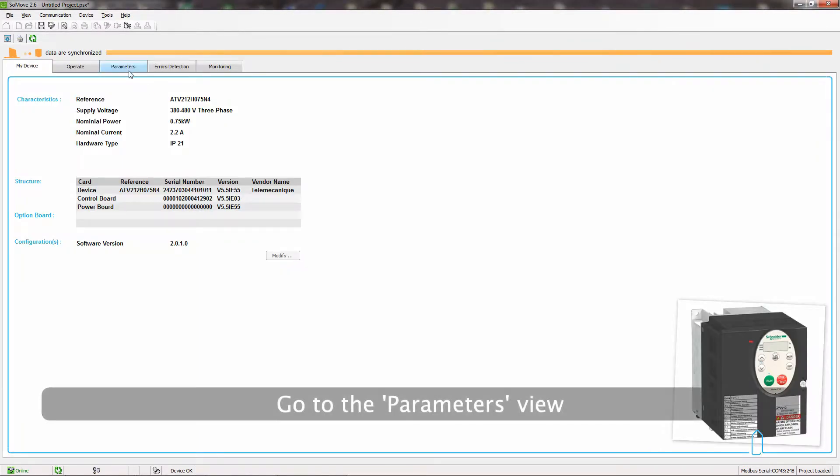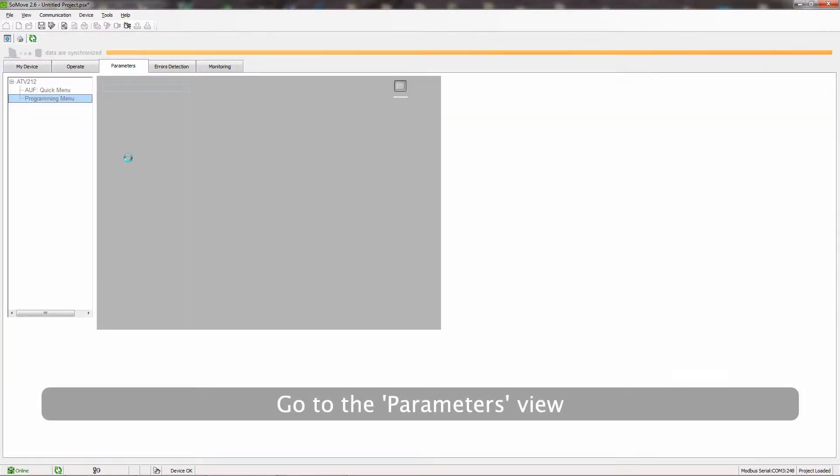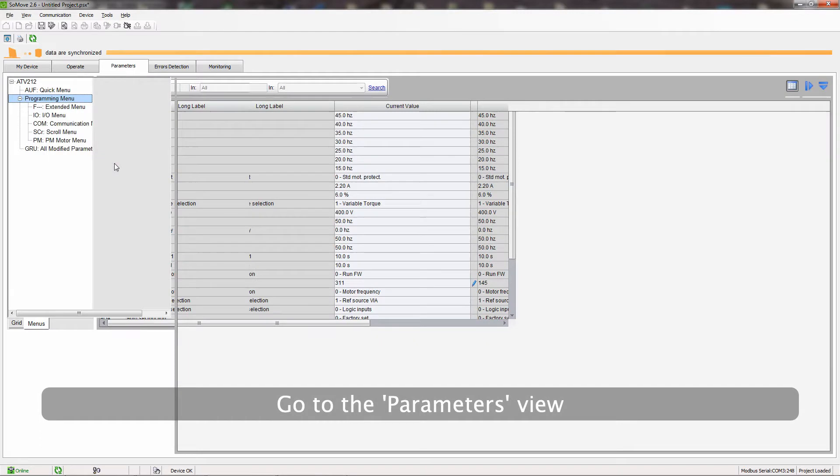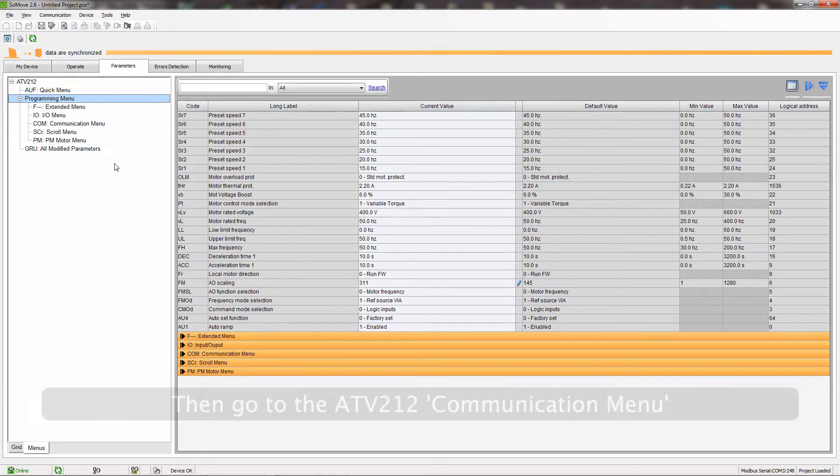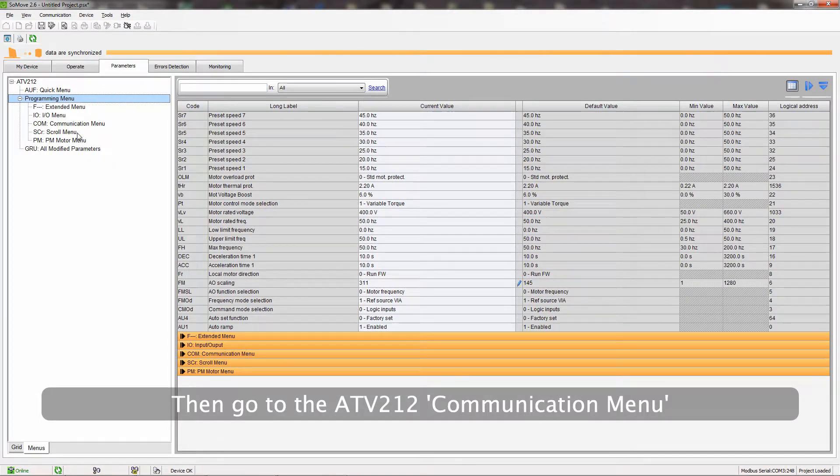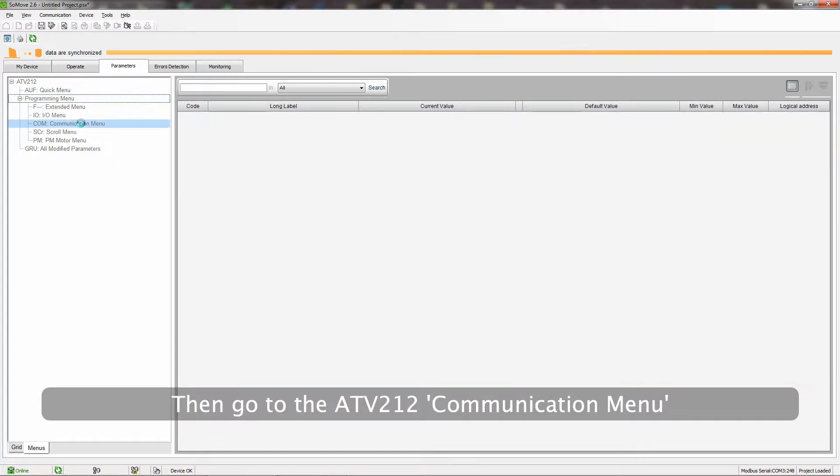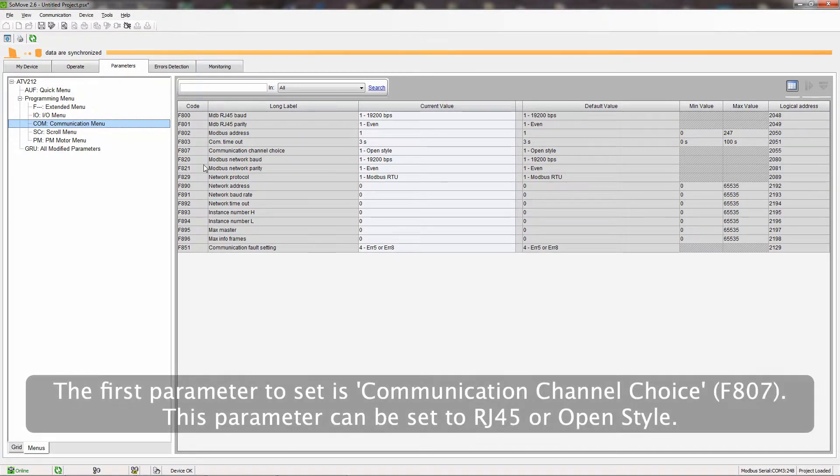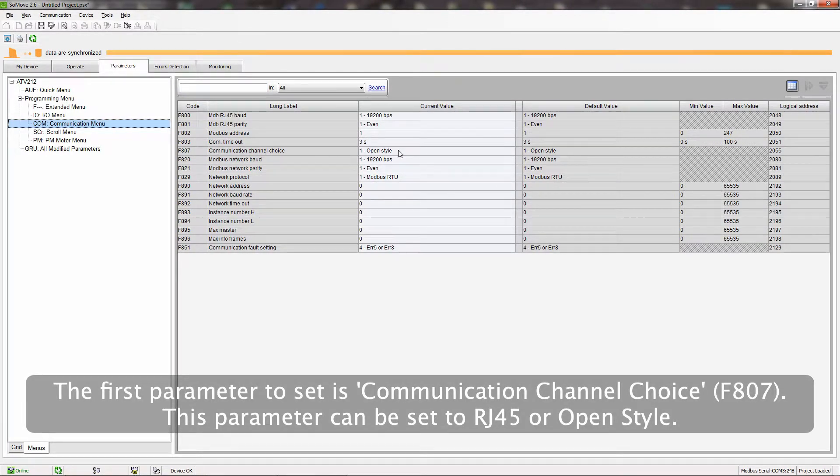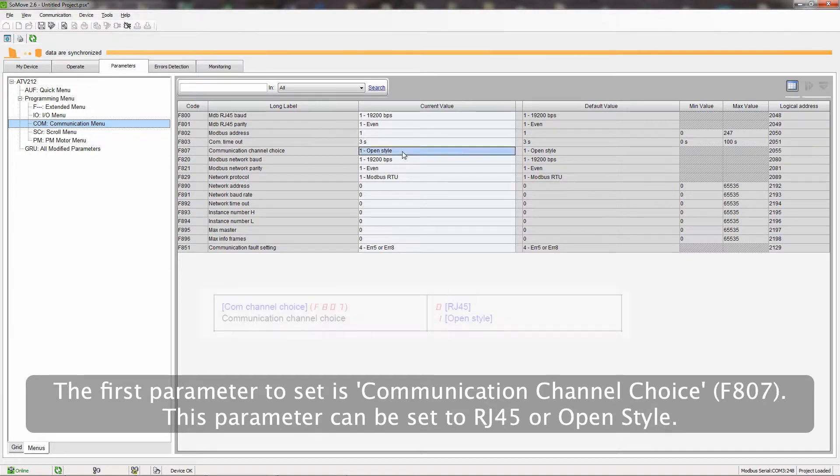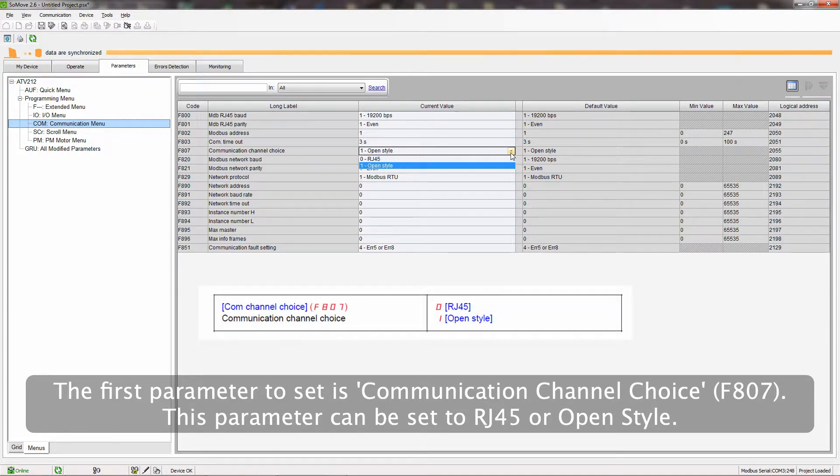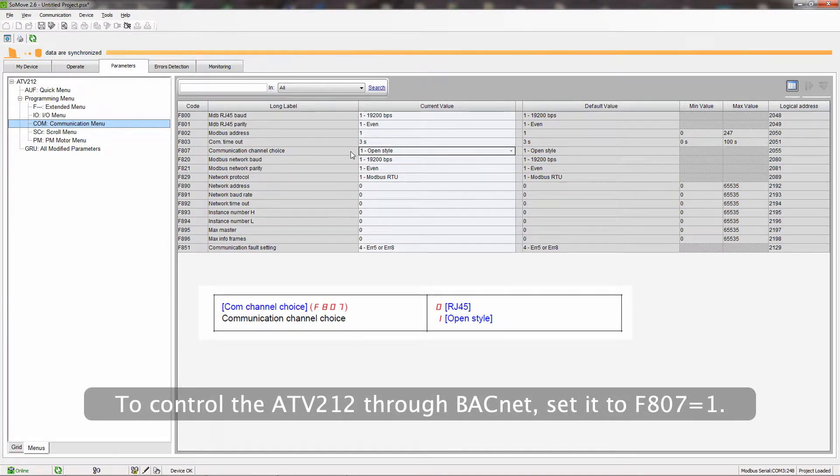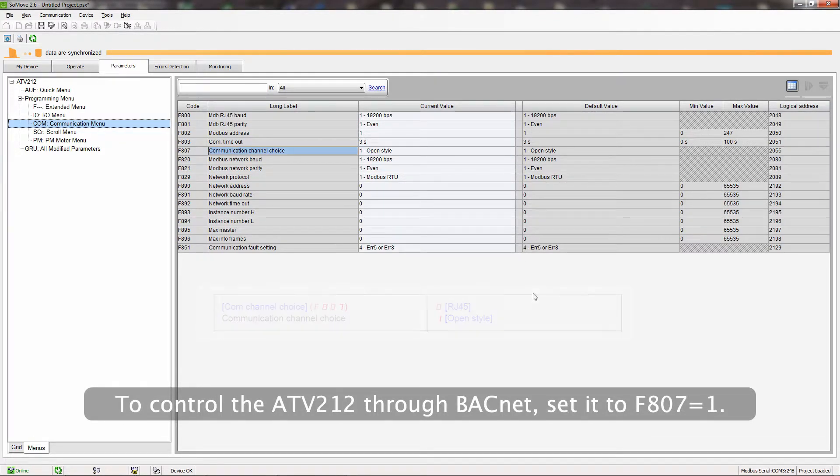Go to the Parameters view. Then go to the ATV212 communication menu. The first parameter to set is Communication Channel Choice. This parameter can be set to RJ45 or OpenStyle. To control the ATV212 through BACnet, set it to F807 equals 1.